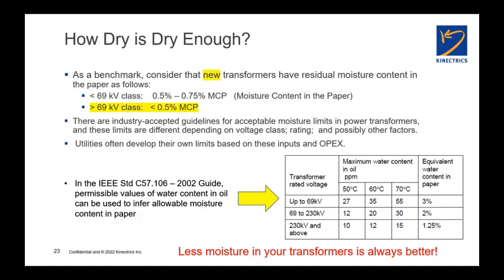But we do know some benchmarks, and a benchmark would be a new transformer. So if you've got a transformer greater than 69 kV class coming from a reputable factory, one that has, for example, a vapor phase dry out system, we know that the moisture content in the paper is going to be 0.5% or less. And below 69 kV, where vapor phase might not be used in the factory, we'd still only be looking at 0.5 to 0.75% moisture content. So those are numbers that we'd associate with a new transformer. As the transformer ages, as we've discussed, those numbers are going to go up. So this is kind of the lower point.